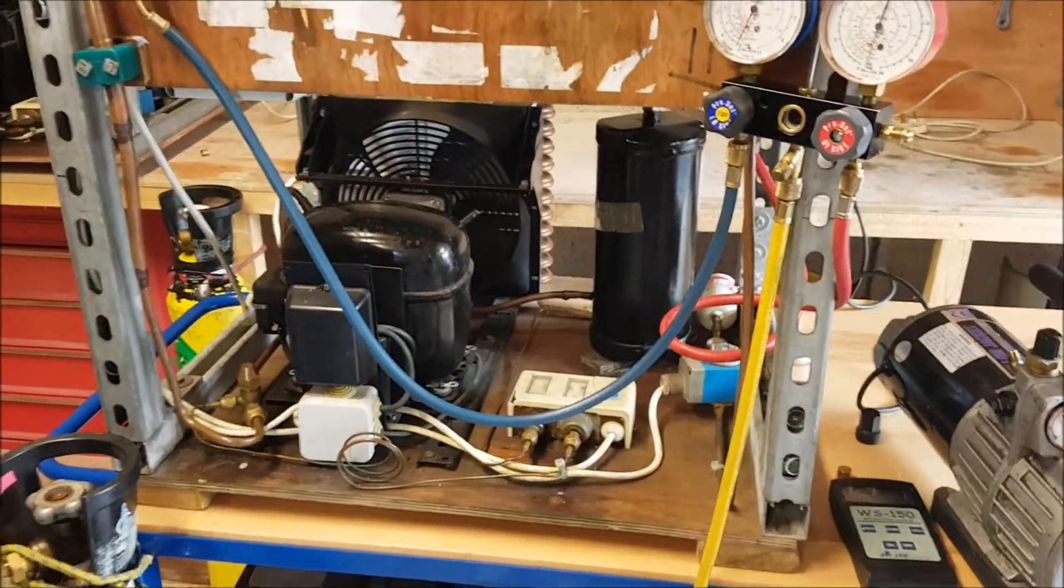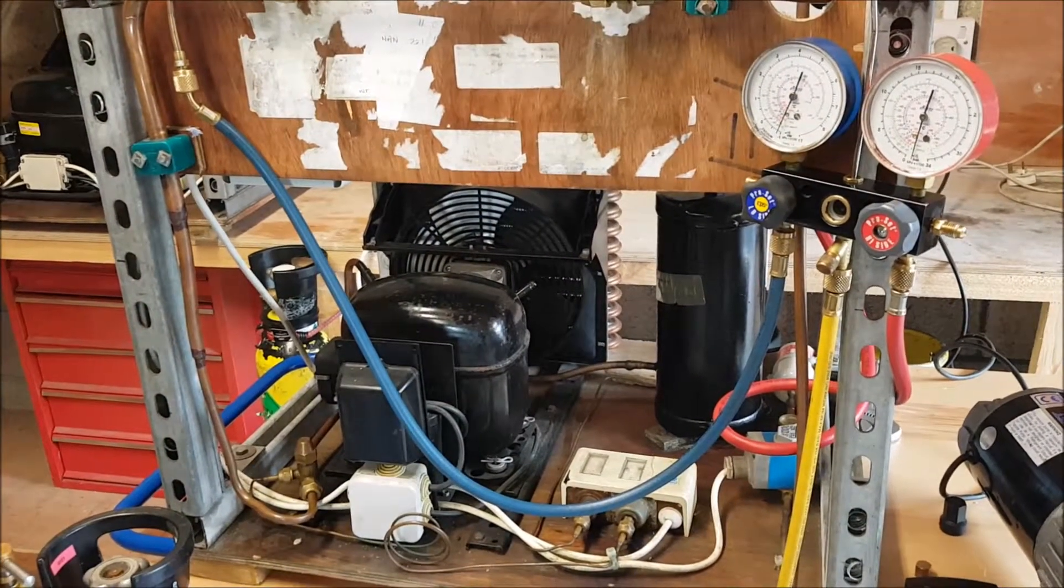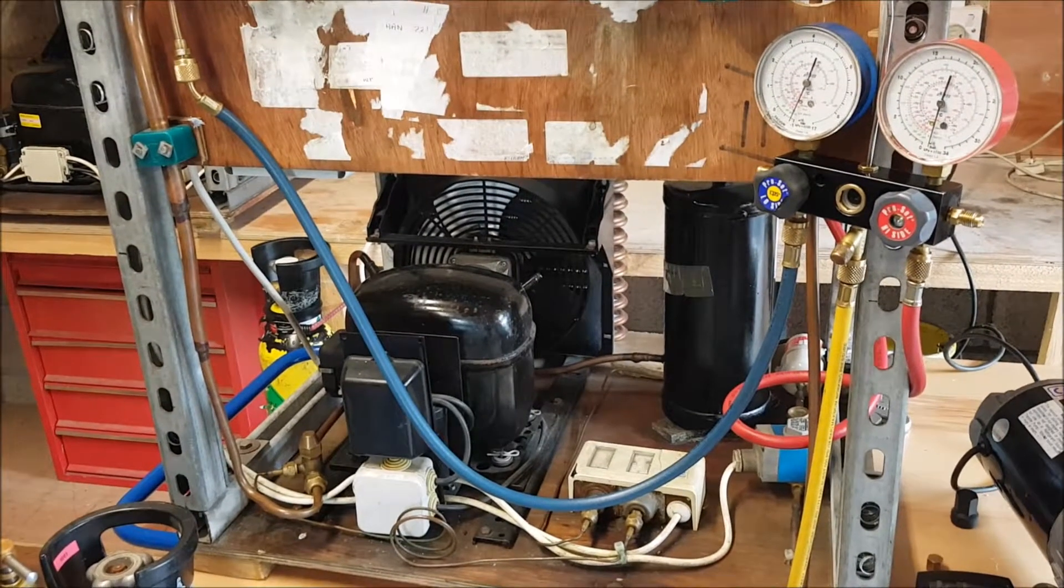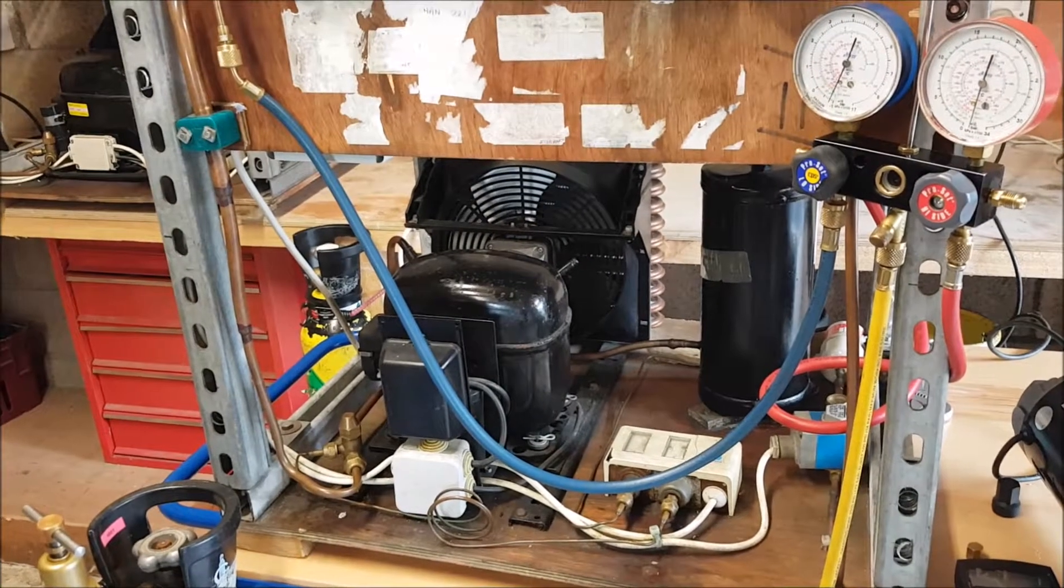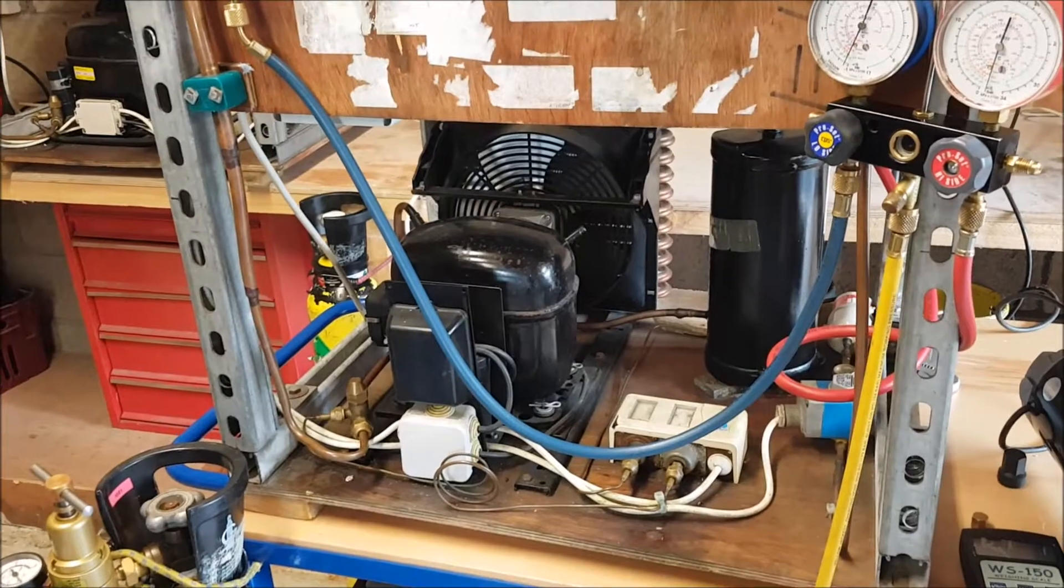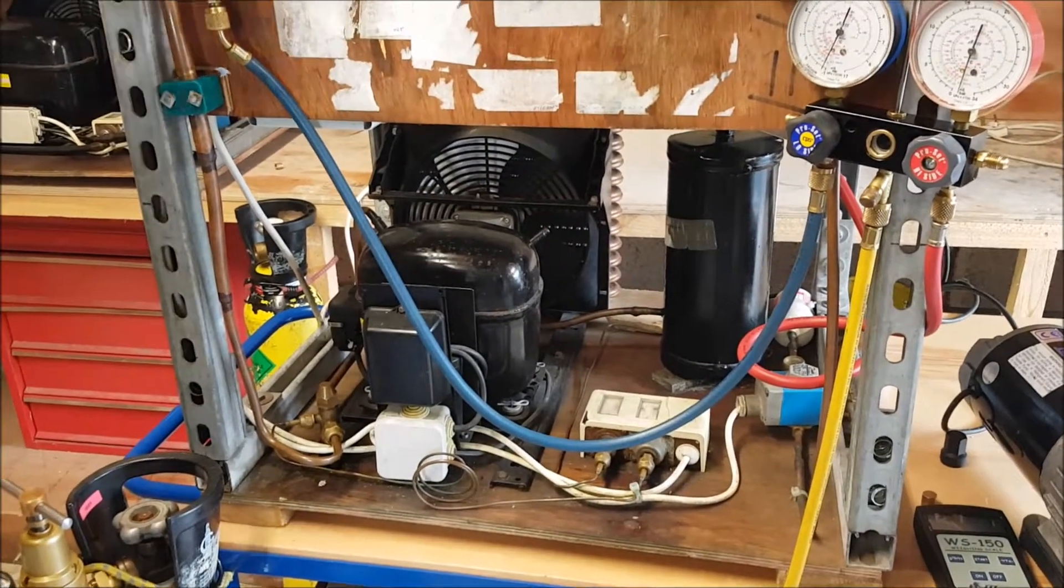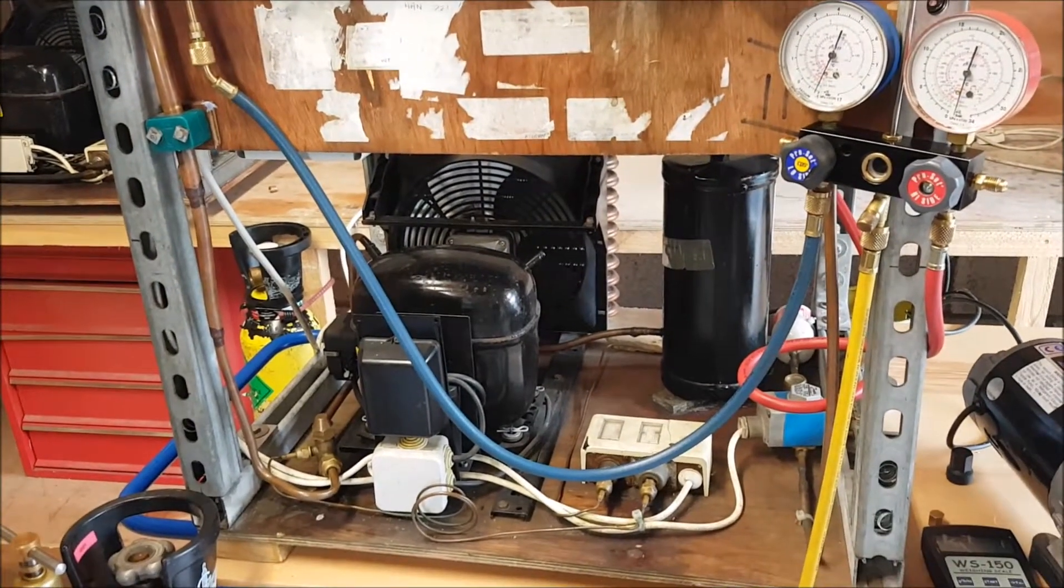I'm satisfied. I'm now ready to charge liquid in. There are two ways of doing this: there's what's called bomb charge and there's called flash charge or initial charge. Bomb charge is that you try and get as much refrigerant into the system, equalize into the high side of the system as much liquid as possible, and then flash in the remaining. Every unit should have a label on it.